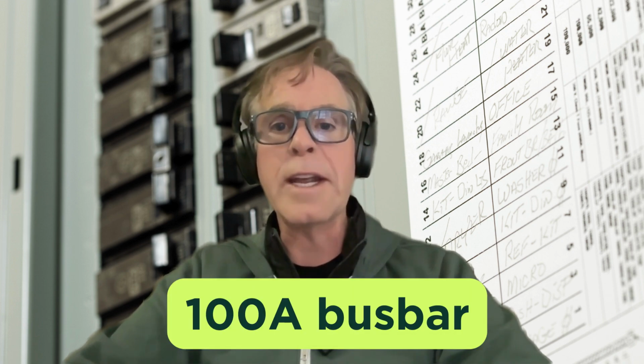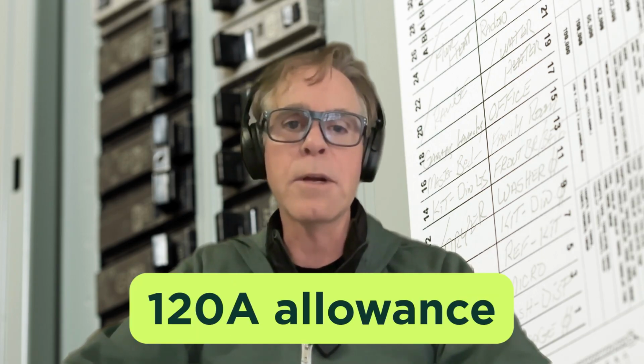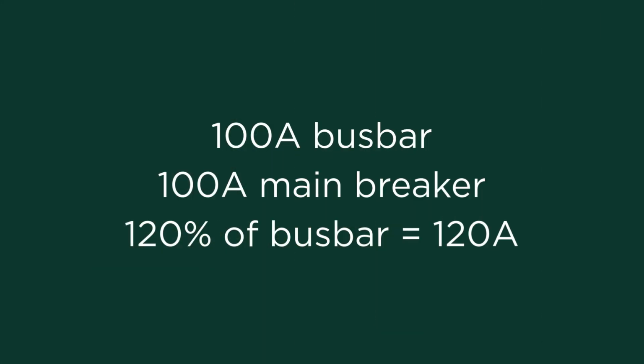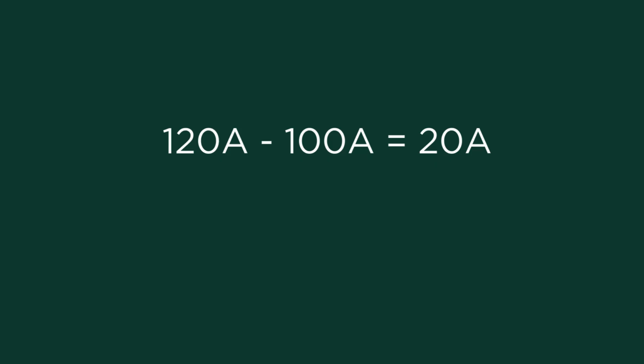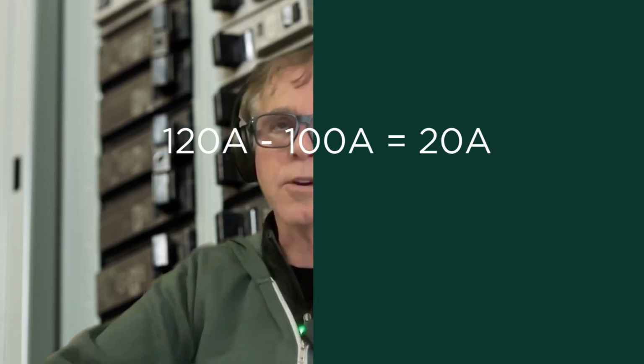So that 120% rule, bus bar is measured in amps. So if we had a 100 amp bus bar, we get 120. That's 120 amps allowance. And we could subtract from that the main breaker. So if you had a 100 amp bus bar protected by a 100 amp main breaker, you could subtract that 100 amp main breaker off that 120% of the bus bar, and that leaves you with 120 minus 100 is 20 amps, and that's your allowance.